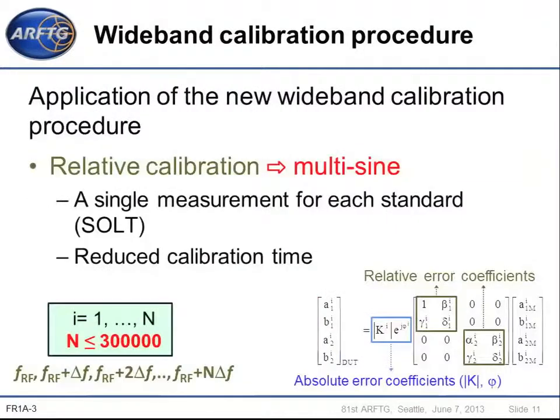The application of this new wideband calibration on the measurement system involves two steps. The first step is a relative calibration — a SOLT calibration using the multi-sine signal. With this calibration procedure, as all the frequencies are generated and measured simultaneously, a single measurement is made for each standard to extract the error coefficients for all the frequency components. This will greatly reduce the calibration time compared to frequency sweeping measurement systems.